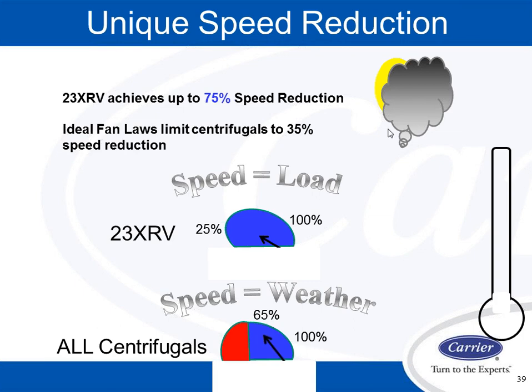And let's say the cloud is hanging over the sun, and then the sun goes up, the tower water temperature goes up, and therefore now the speed of my centrifugal will have to increase, because the wet bulb temperature in the tower has gone up. On a centrifugal, the VFD tracks the wet bulb temperature outside. Whereas on the 23XRV, speed equals load. It is the only part load, part lift chiller in the marketplace.